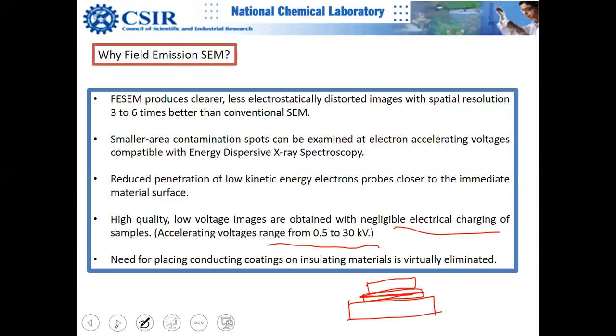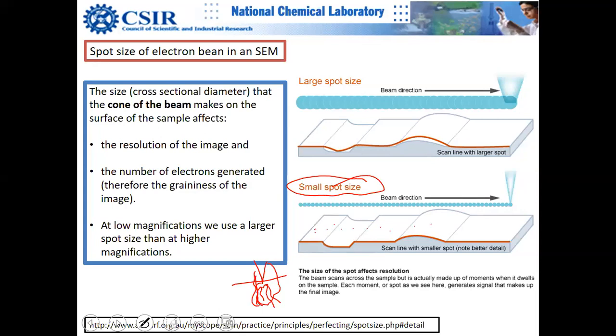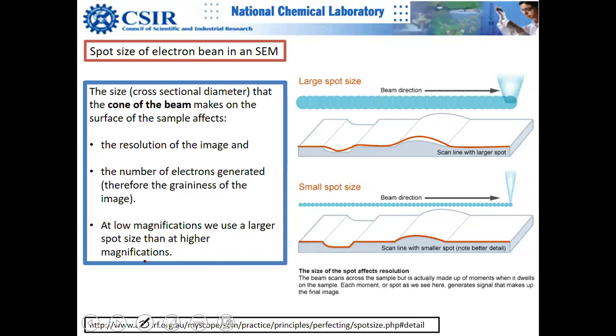Resolution is also a function of the type of atoms present in the specimen, because the random pathways of outgoing secondary electrons are governed by the type of scattering interactions between outgoing electrons and atoms, including crystallinity. Atomic number and everything else besides spot size contribute to resolution — there is no simple thumb rule.